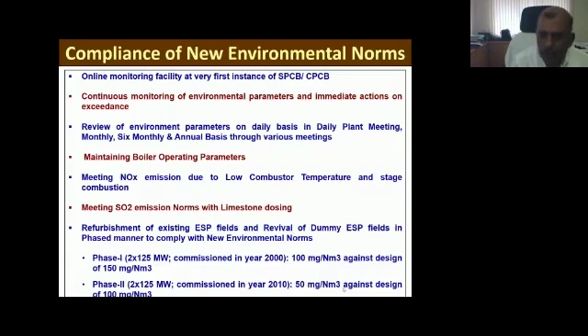This has helped in compliance with particulate emission. The design of our phase 1, that is 2 into 125, or 250 megawatt, commissioned in 2000, was for 150 mg per NMQ, but now the norm is 100. The new environmental norms requirement is 100 mg NMQ. Similarly, for phase 2, commissioned in 2010, the design was 100 mg NMQ, but the new norms now require 50 mg NMQ. So this is a major challenge for compliance.